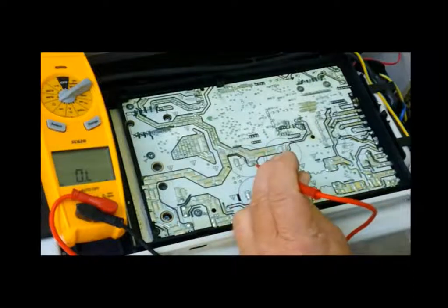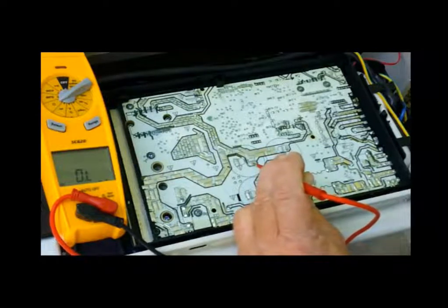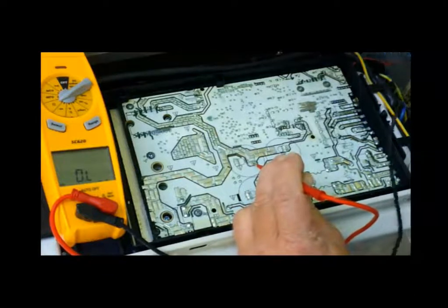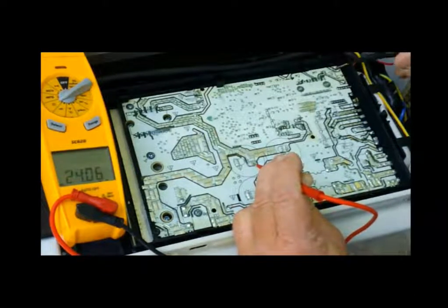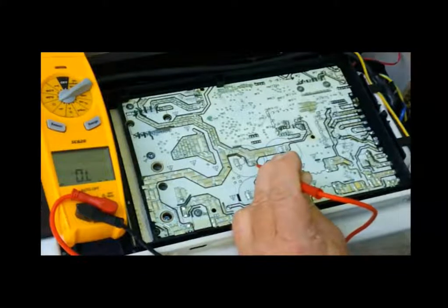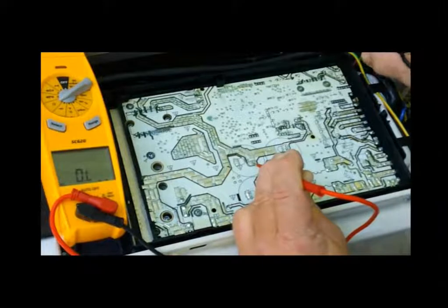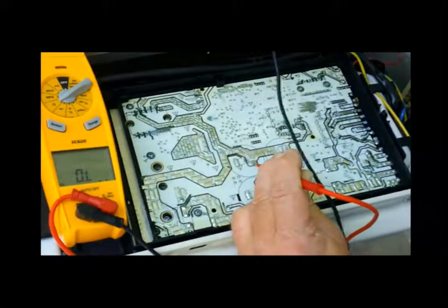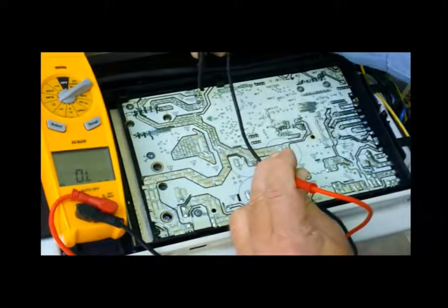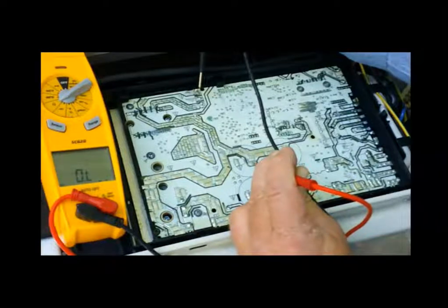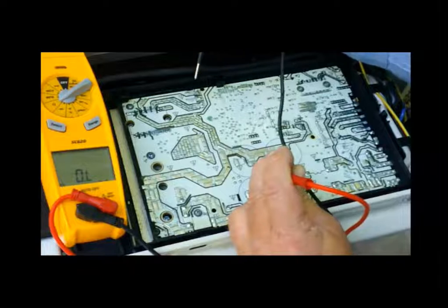Now you can either use your schematic or your wiring diagram to find it, to see where that's at, or you can take the board over and flip it over, or you can actually look and see what you've got. So we've got 3 here, which is going to signify our UVW on this, but this goes to our fan, because when we look underneath of it, it hooks up to this wire here, which goes over to our fan. Now, I did some checking. This right here, this patch is going to be the UVW for our compressor. So we're simply going to go to each one with our negative lead.